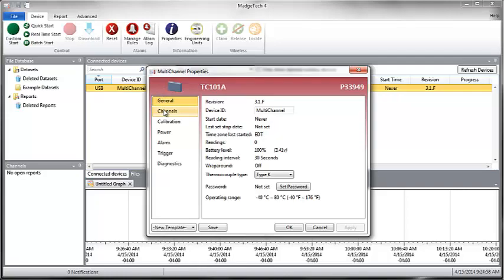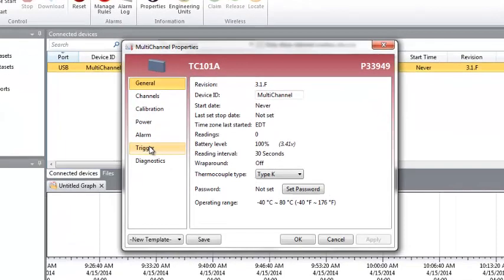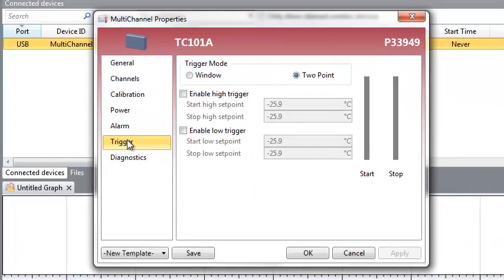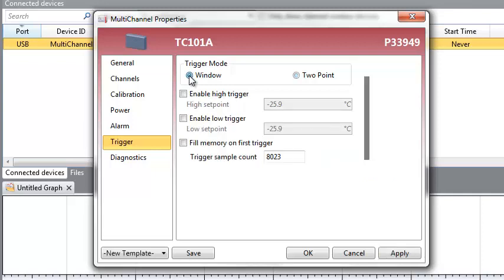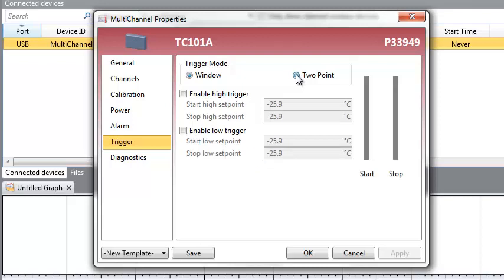Within the Properties palette, select Trigger to display the options. If you do not see trigger in the list, it can be assumed that your device does not support this feature. When configuring the trigger settings on your device, you have the option of selecting Window Mode or Two-Point Mode. Window Mode allows for one range of data to be recorded based on a high and a low set point. Two-Point Mode allows for two different ranges of data to be recorded, each range having its own high and low set point.